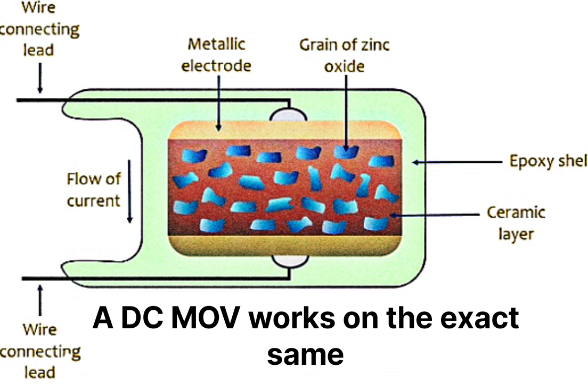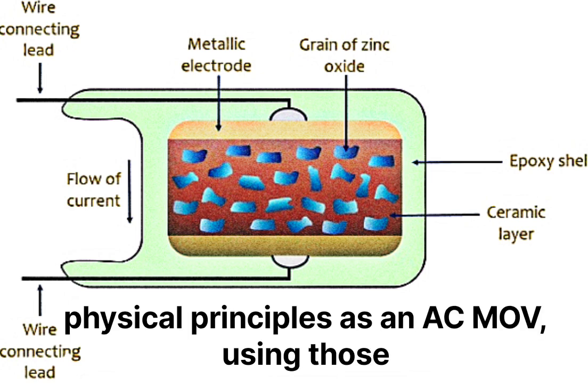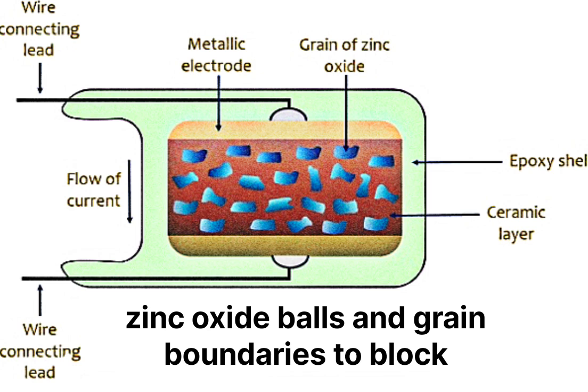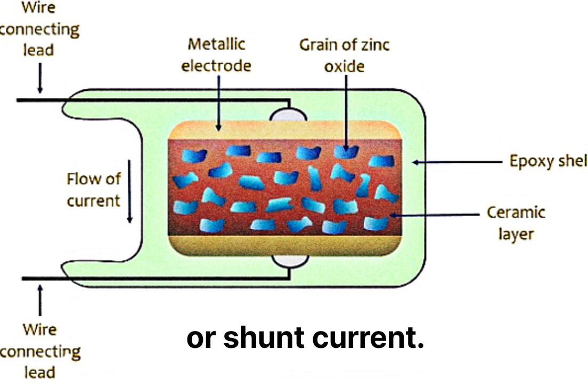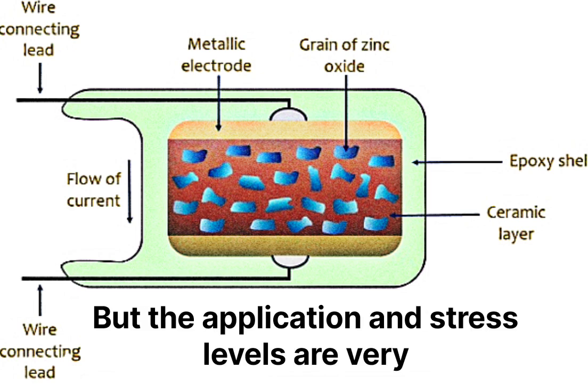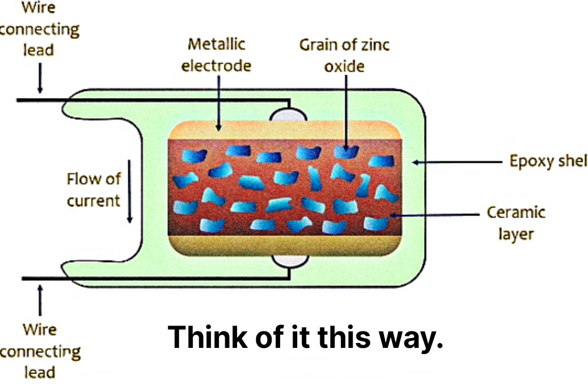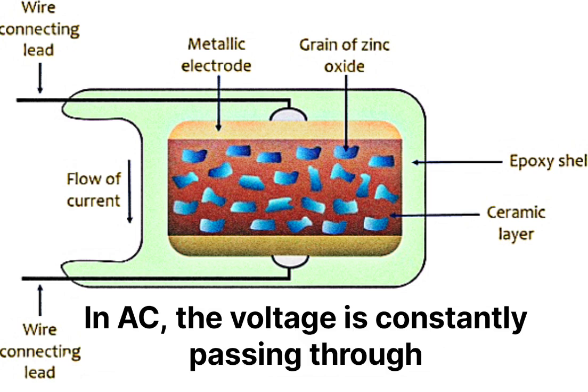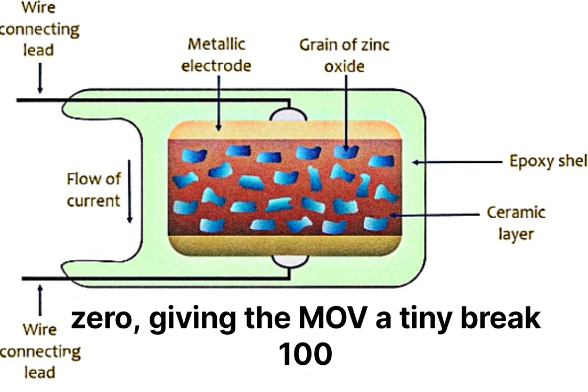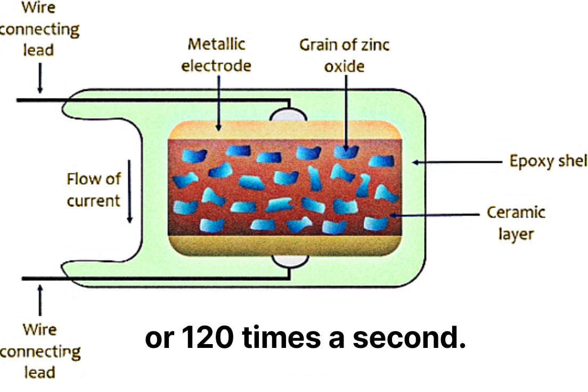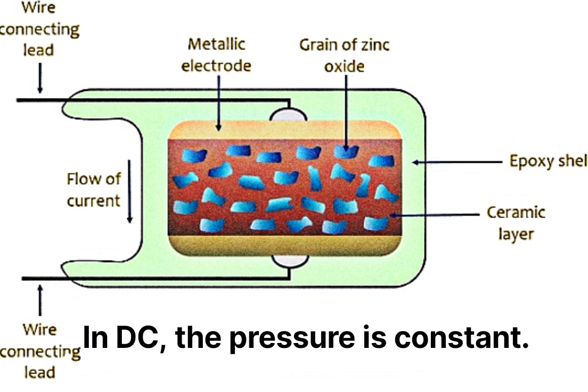A DC MOV works on the exact same physical principles as an AC MOV, using those zinc oxide balls and grain boundaries to block or shunt current. But the application and stress levels are very different. Think of it this way. In AC, the voltage is constantly passing through zero, giving the MOV a tiny break 100 or 120 times a second. In DC, the pressure is constant.